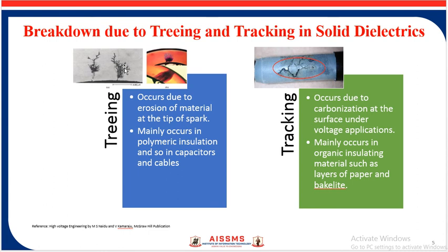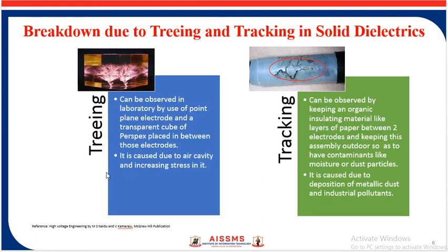As time passes, the breakdown channel spreads into the insulation in an irregular tree-like fashion, leading to the formation of conducting channels. This kind of channeling is called treeing. Under AC voltage conditions, treeing can occur in a few minutes or several hours. Hence, care must be taken to see that no series air gaps or other weaker insulation gaps are formed. Usually, tracking occurs at very low voltages of the order of about 100 volts, whereas treeing requires high voltage.